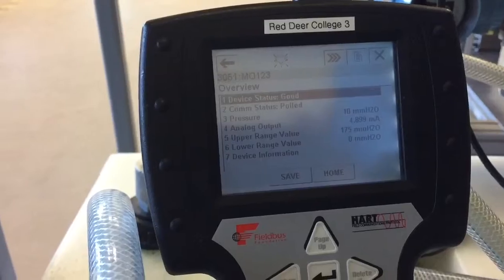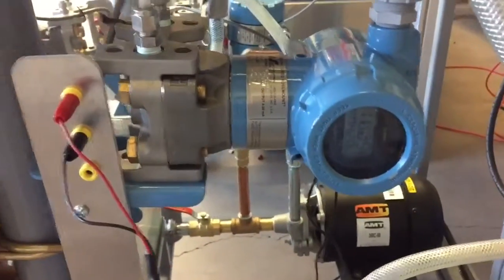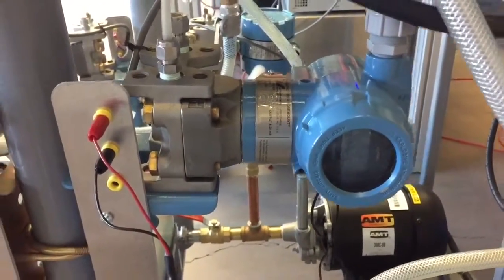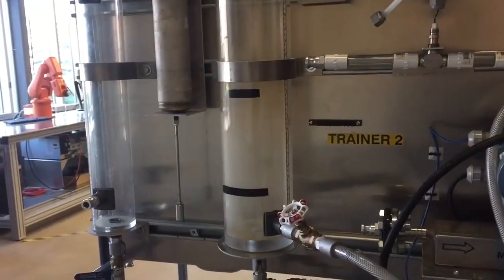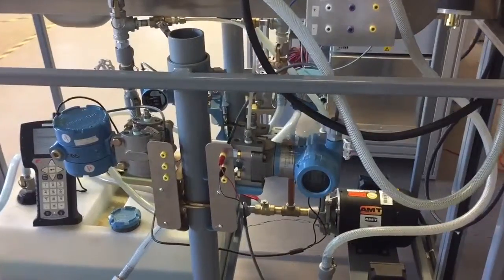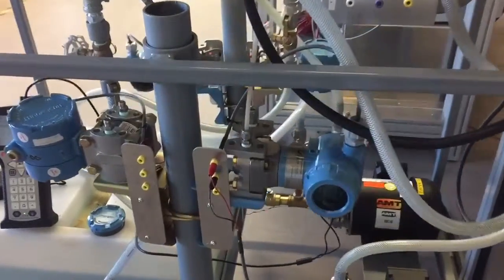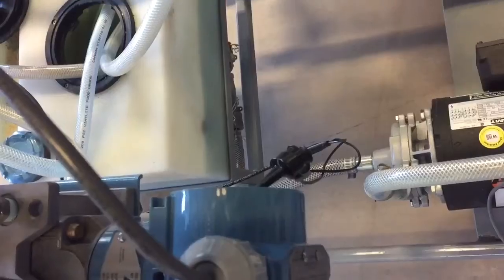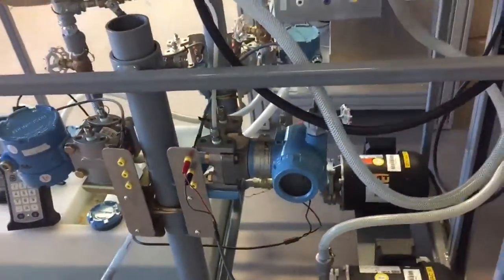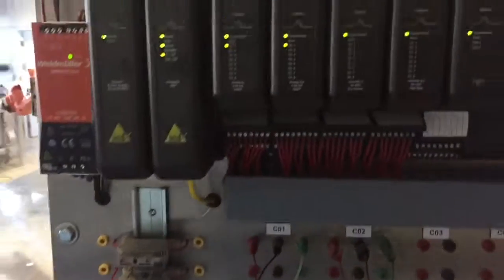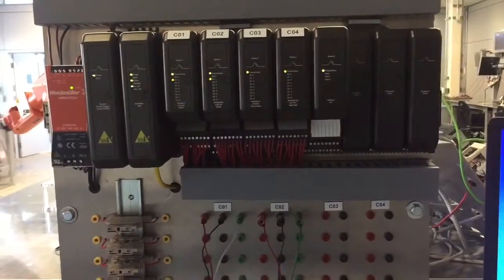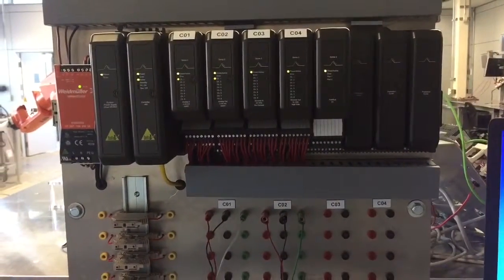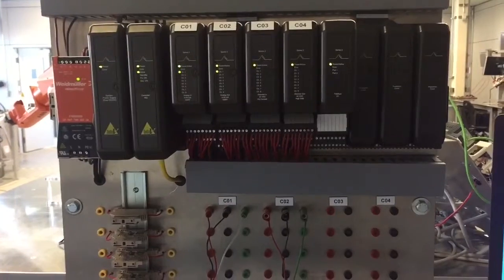That is from this transmitter here, this pressure transmitter that is set up to measure level in one of these vessels on our process trainer. The HART communicator right now is currently connected to the back of the pressure transmitter so we can communicate with it, and the transmitter is wired into our DeltaV process trainer right here.